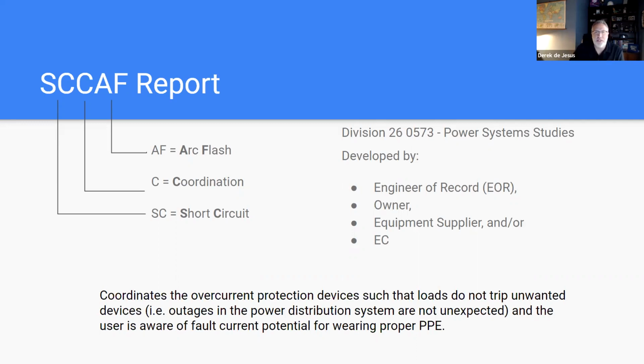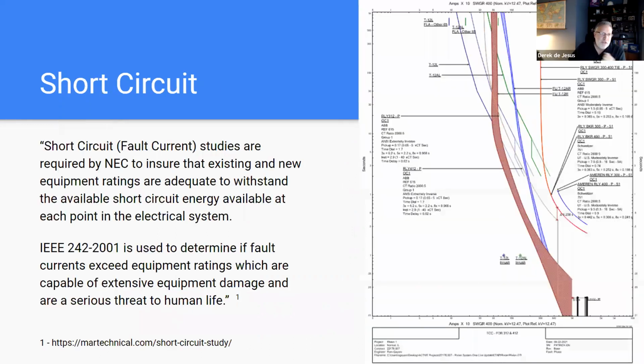And that rolls into the coordination study for setting your breakers, which is then combined, and then you get an arc flash hazard analysis. So the short circuit study looks at the full circuit of your system from your utility feeds all the way down to your largest motors, your transformers, your feeder panels, to ensure that if you have a fault, your devices will properly be staged and staggered, that you're tripping the first available overcurrent protection device, right? You're trying to prevent a large loss of damage to equipment and obviously to people, right? Personnel and safety. That's why the SCCAF report is really an EH&S tool.